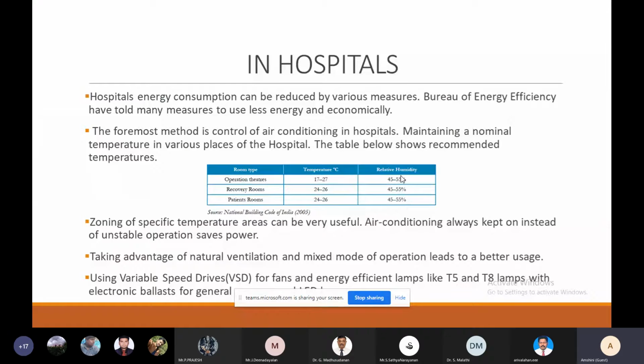In operation theaters, you can use lower temperatures like 17 to 27 degrees Celsius, and 24 to 26 degrees for recovery rooms and patient rooms. Specific temperature zoning can be useful. Keeping air conditioning always on instead of unstable operation saves power. Taking advantage of natural ventilation and mixed mode operation leads to better usage.